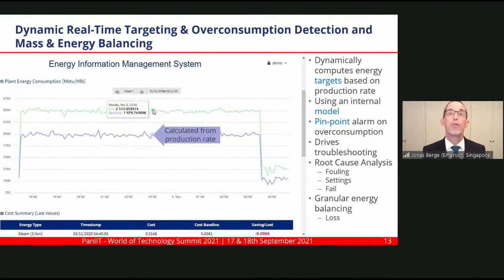Let's say you're a refinery running at 250,000 barrels per day. Based on that production rate, the model calculates what should be the consumption of water, air, gas, electricity, steam, and other utilities, and compares that against the actual measured consumption.